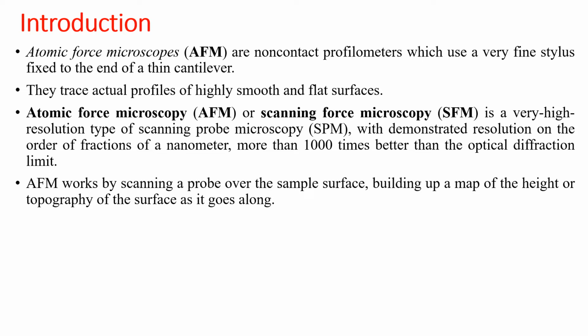Atomic force microscopy is also called scanning force microscopy, that is SFM, which is of a very high resolution type, more than 1,000 times better than the optical diffraction limit. This AFM works by scanning a probe over the sample surface, building up a map of the height or topography of the surface as it goes along. It means that the information is gathered by feeling or touching the surface with the mechanical probe. This atomic force microscopy works on the principle of van der Waals force. That we will see in detail.